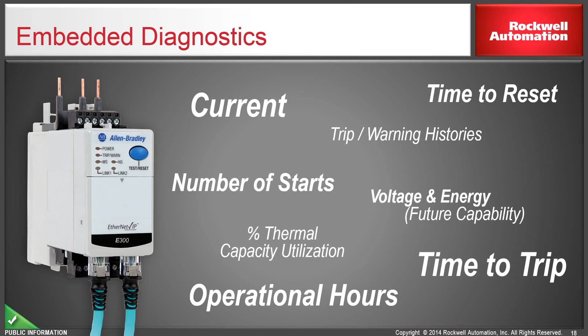So this is the modular design which I was talking about. On the right-hand side, if you see down the line, there is a sensing module which senses the motor current, and on top of it is a control module, which has a base module with integrated inputs and outputs, and on top of it is a communication module which has some diagnostic information and dual port Ethernet communication capabilities, right? The current sensing module comes in various ranges. If you want current sensing only, it is available in current. If you want ground fault and current, then there is a separate sensing module. If you want voltage, current, ground fault and power, then there is a separate one. So there is modularity and scalability depending on the need.